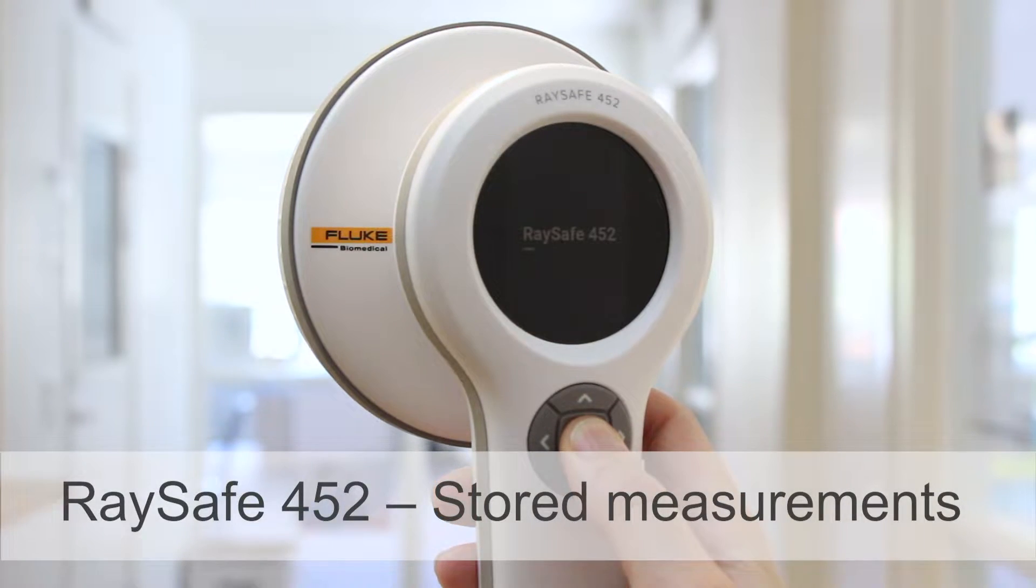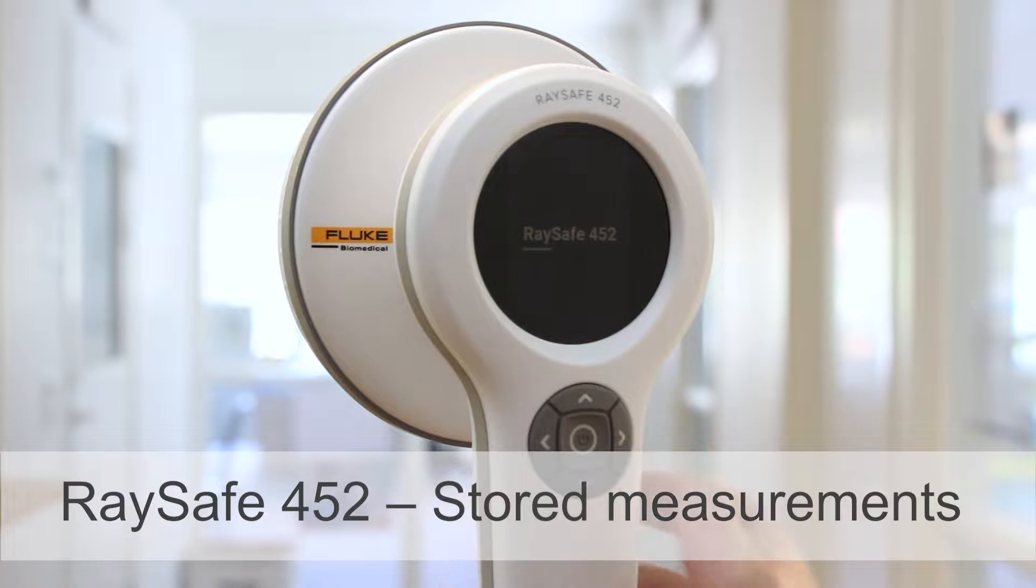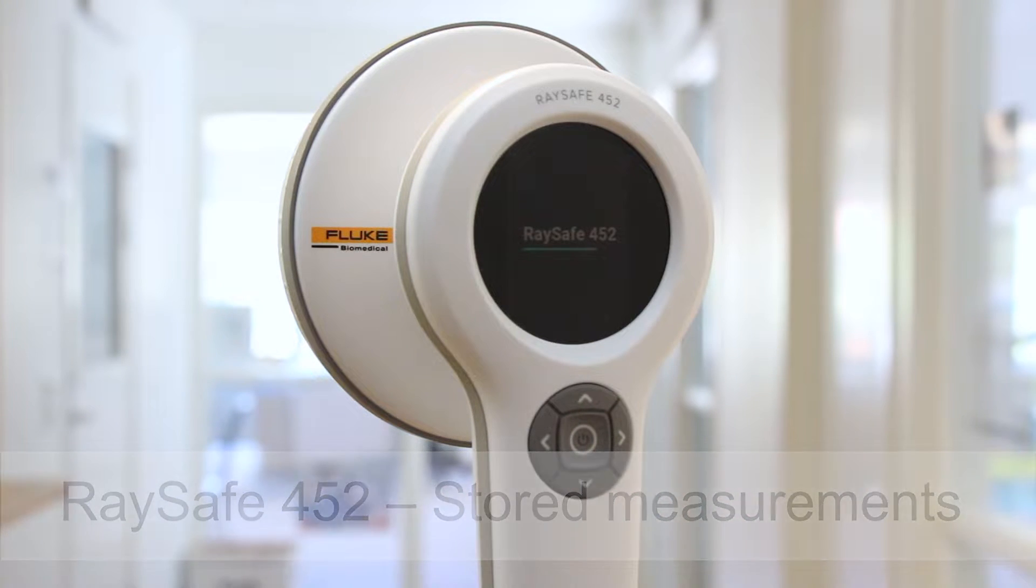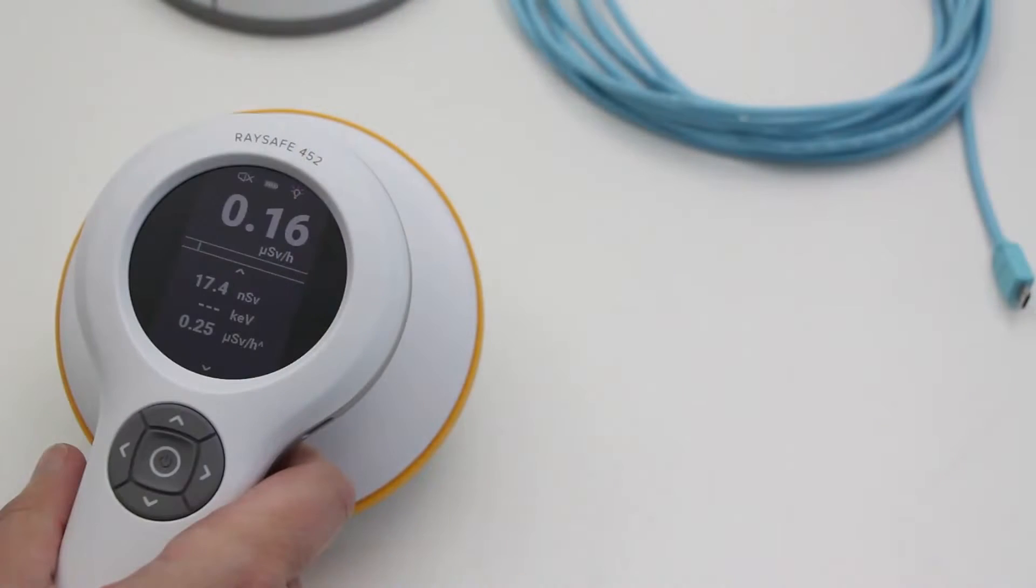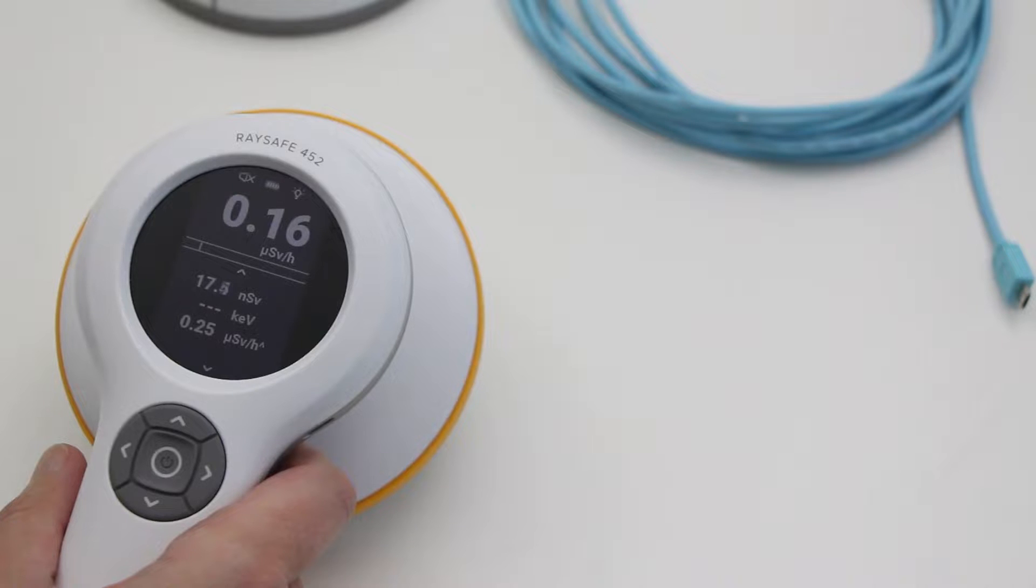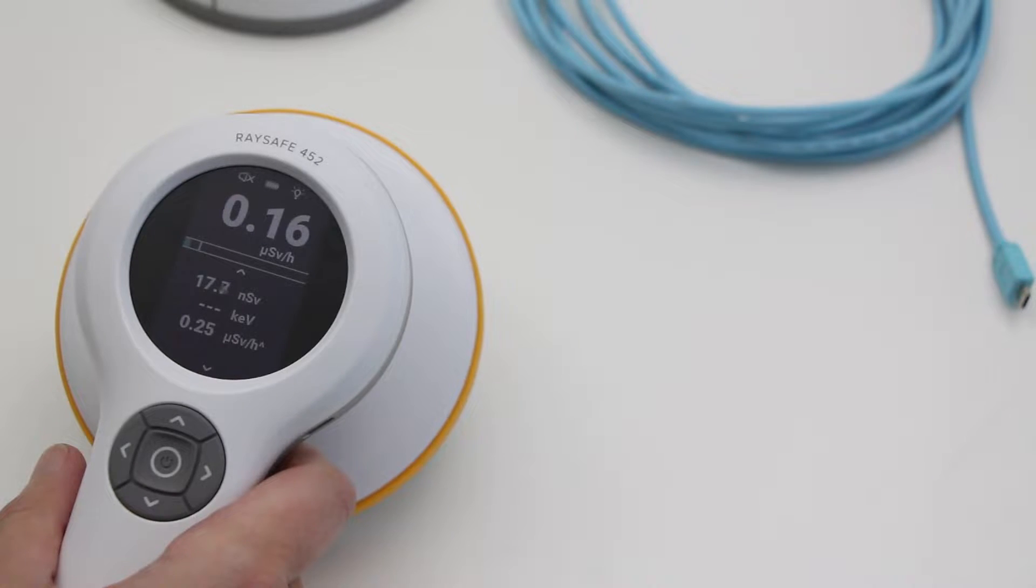This time we take a look at how to work with stored measurements in the RaySafe 452. The RaySafe 452 automatically saves a log of the dose rate or count rate with 1 second resolution from power on to power off.